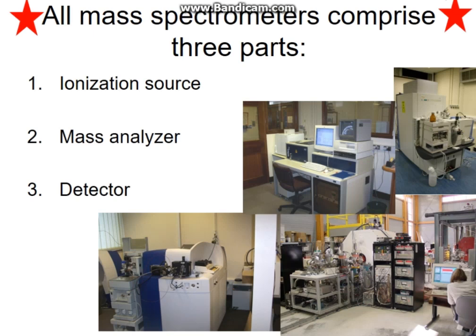All mass spectrometers comprise three parts — note the red stars. There's the ionization source, where the ions are generated; the mass analyzer, where the ions are separated according to their mass-to-charge ratio; and the detector, where the ions are detected. There are many different types of mass spectrometer using different electric or magnetic fields to separate ions and different ways to generate and detect ions, but they all share these three fundamental parts.